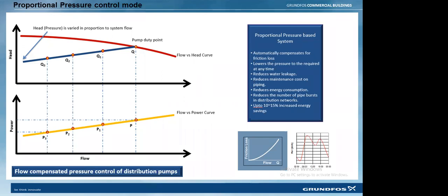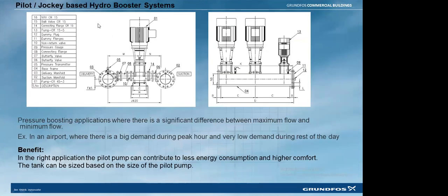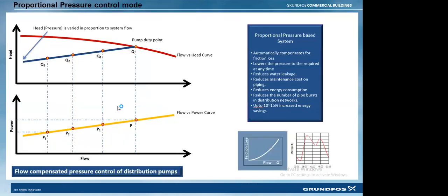Even nowadays, hydropneumatic systems are designed for very high pressure, high rise buildings. Your system will be highly pressurized, and your pipelines will be stressed with the higher pressure, which leads to leakages or breakages in the pipeline. Wherever you have a weak joint, coil, gaskets, or other parts, it will get broken. To avoid that, we have a functionality called proportional pressure control. Our mindset has to shift from constant pressure control to proportional pressure control, which will give a better control in the system. Next slide.